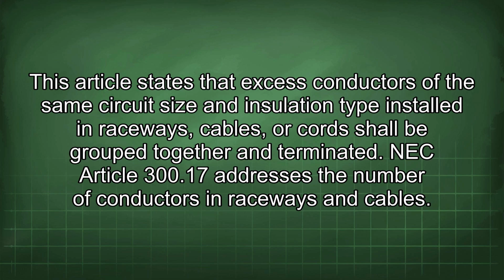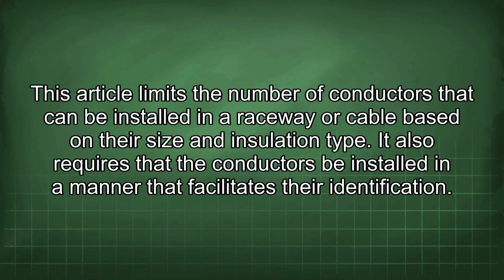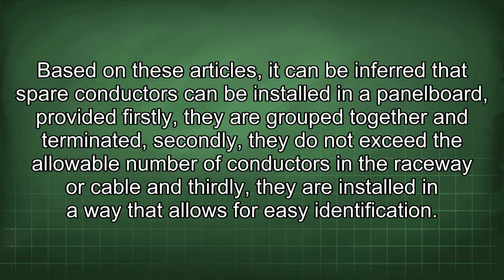NEC Article 300.17 addresses the number of conductors in raceways and cables. This article limits the number of conductors that can be installed in a raceway or cable based on their size and insulation type. It also requires that the conductors be installed in a manner that facilitates their identification. Based on these articles, it can be inferred that spare conductors can be installed in a panel board, provided firstly, they are grouped together and terminated, secondly, they do not exceed the allowable number of conductors in the raceway or cable, and thirdly, they are installed in a way that allows for easy identification.